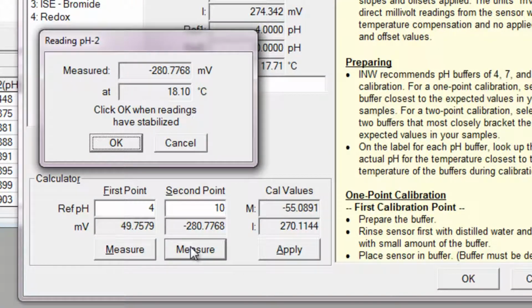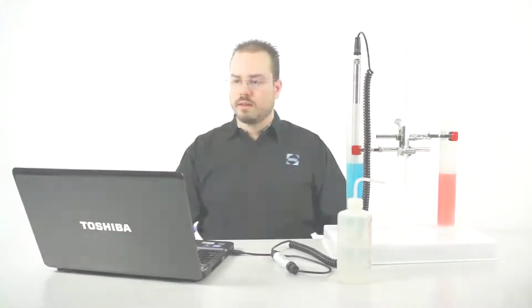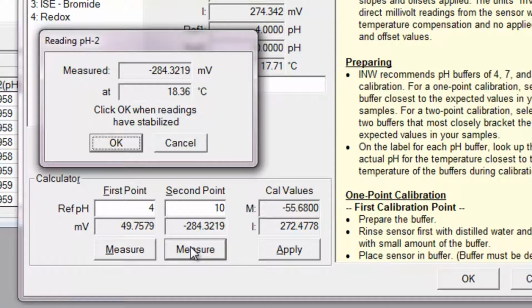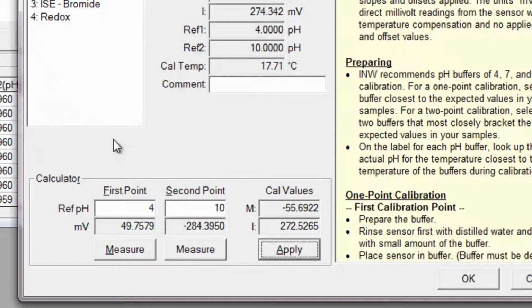And then you'll want to wait typically 5 to 15 minutes for stability in the second point. And now we wait. You'll know when you've reached stability when the millivolts are slowly dropping in the lower decimals, the hundredths to the thousandths. And it'll reach a point where you'll see the millivolts bounce up and down between 2 points. And right here it looks like we are stable in our second point. We'll click OK to accept the value.